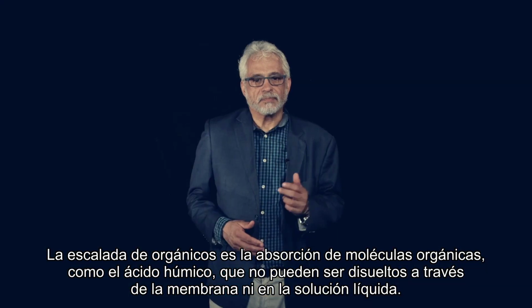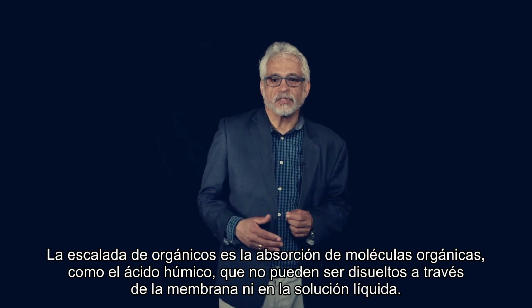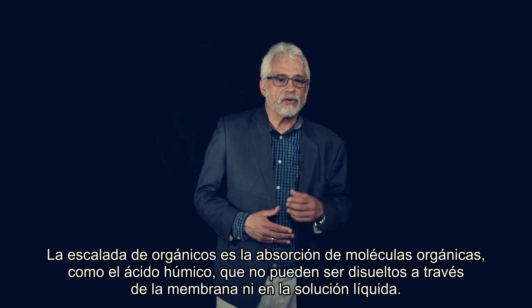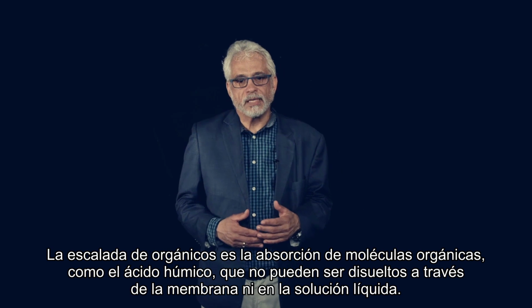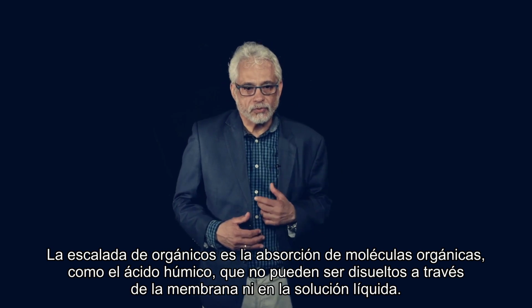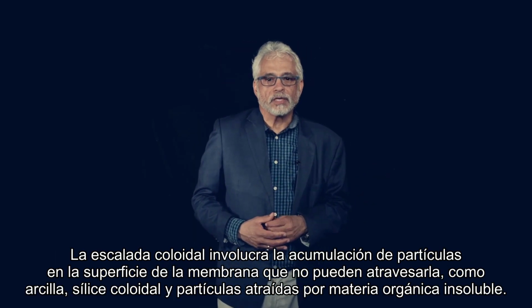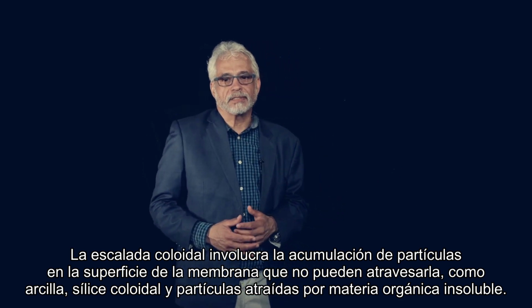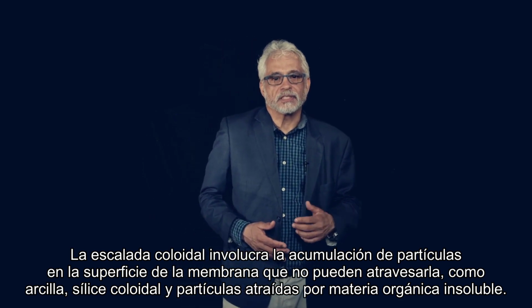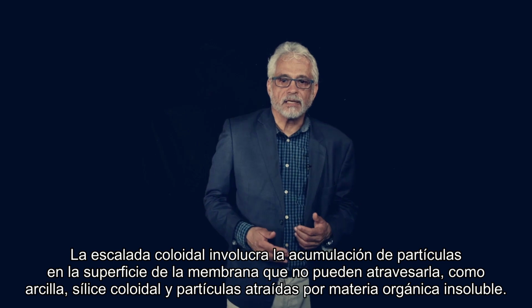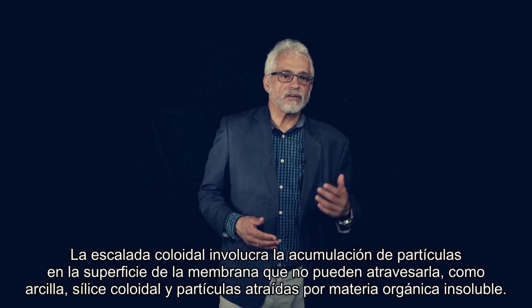Organic fouling is absorption of organic molecules such as dissolved humic acid, which are unable to diffuse through the membrane or redissolve into the feed bulk solution. Colloidal fouling involves coating of the membrane surface by particles that cannot pass through the membrane, such as clay, silt, colloidal silica, and particulates attracted by undissolved organic matter.